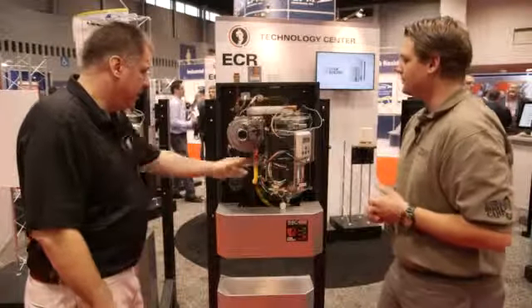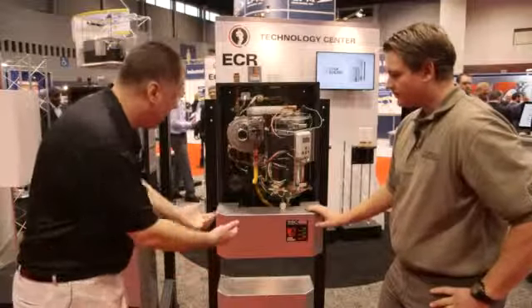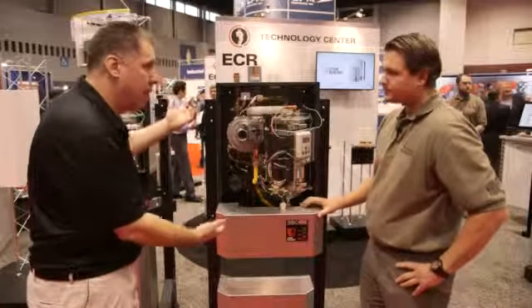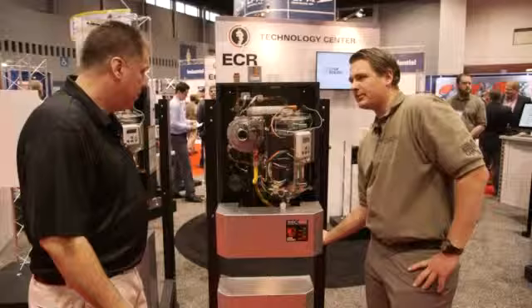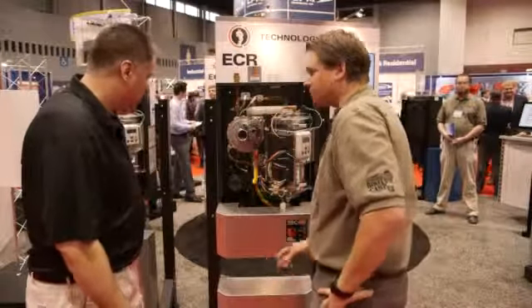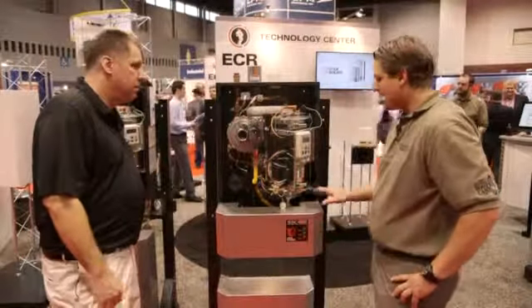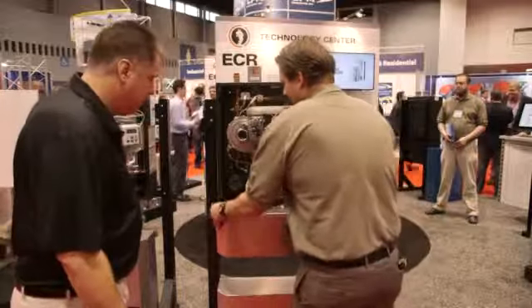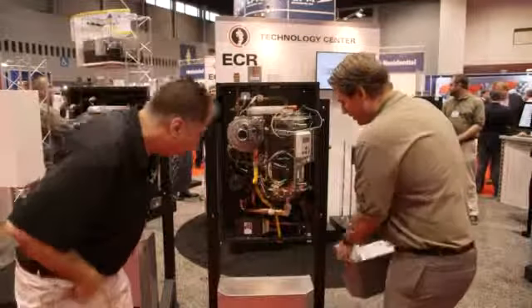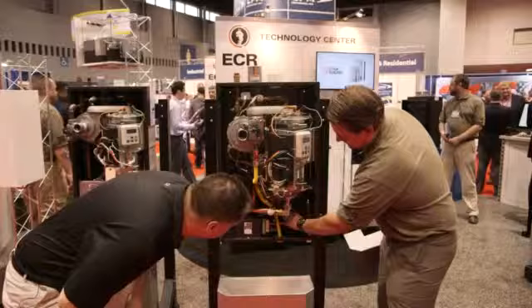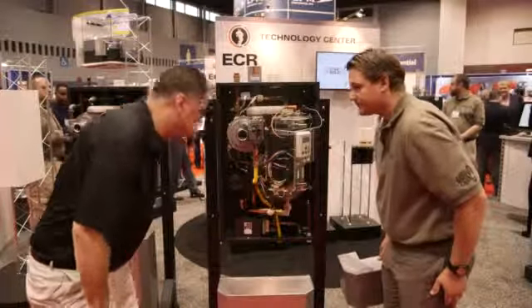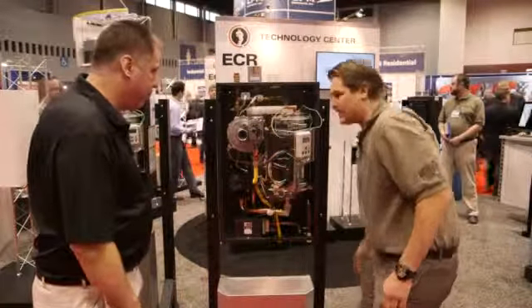Right. And I see you've got the gas shutoff valve. The gas comes in the bottom. Gas comes in the bottom on this one. Top or the bottom or either? Connections are on the bottom for this one. Gas is on the bottom. Drains on the bottom for the condensate. This actually has a condensate trap built into the base of the boiler down here. So that's built in. Really simplifies things. It simplifies the piping. Yes, it does.